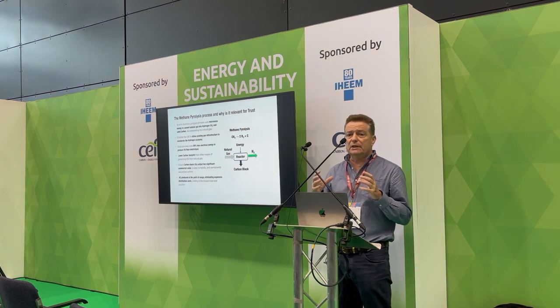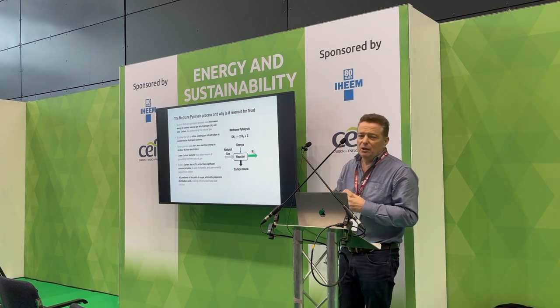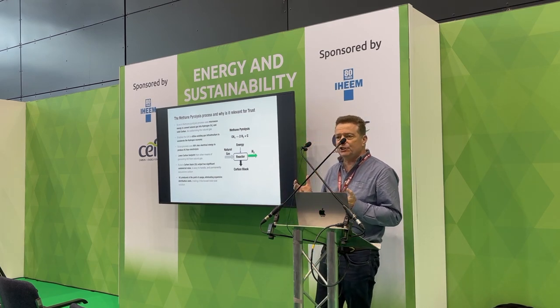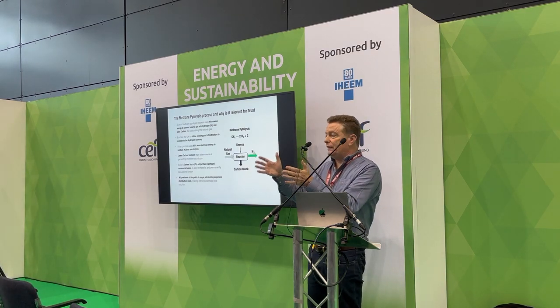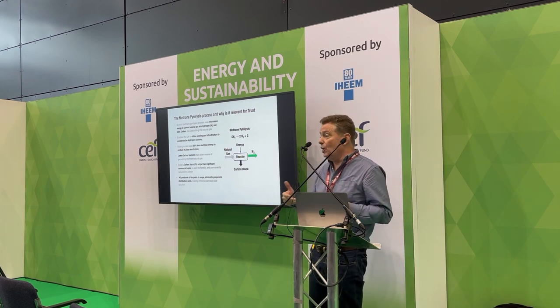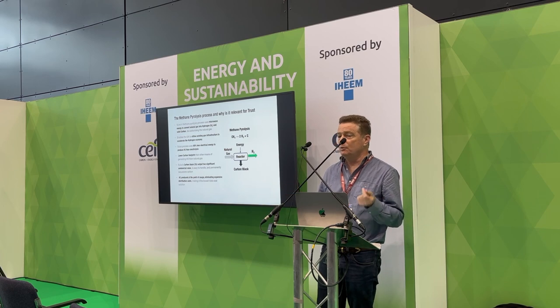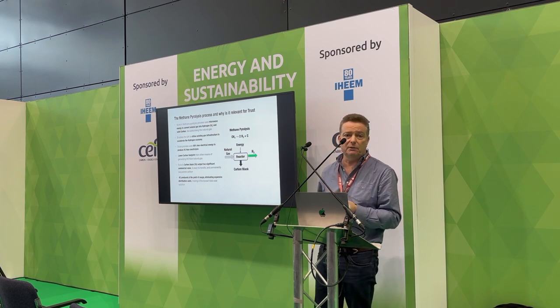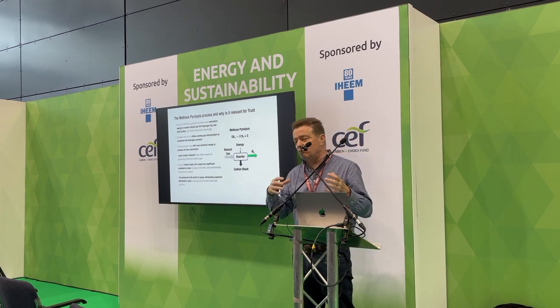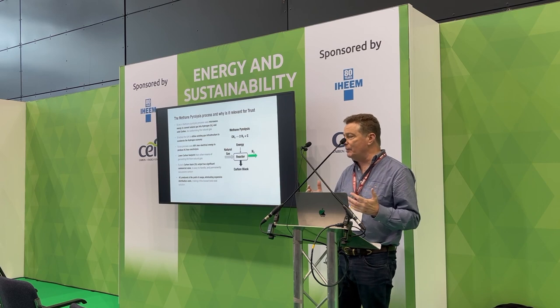We have a very low footprint system. We make the hydrogen on site, so it's not shipped to you, it's not brought in cylinders, it's not piped in. Wherever you've got a gas connection we can put our shipping container right there — it feeds low pressure, medium pressure gas. We can put it in your back garden if you wanted. We take three-phase electricity and produce hydrogen which feeds straight into the boiler, or we can put it into storage. The carbon black we will deal with — we'll take it away and manage it, so you have no requirement to deal with the carbon.